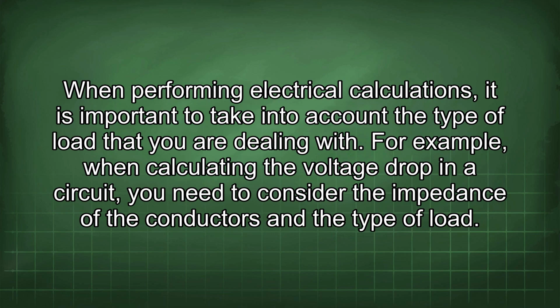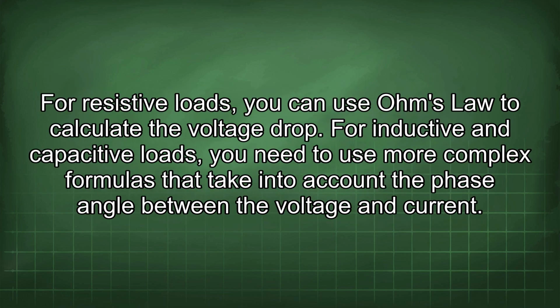When performing electrical calculations, it is important to take into account the type of load that you are dealing with. For example, when calculating the voltage drop in a circuit, you need to consider the impedance of the conductors and the type of load. For resistive loads, you can use Ohm's law to calculate the voltage drop.